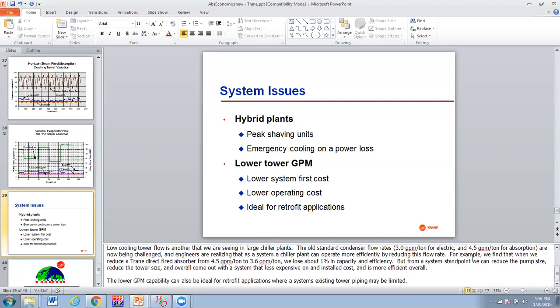Okay, and they mentioned that this lower GPM capability, if you're going to retrofit, you've already got pipes in, and the pipes weren't sized for the 4.5 GPM per ton, but you may be able to cram 3.6 because they were probably designed for 3.0. So anyway, lots of good information.